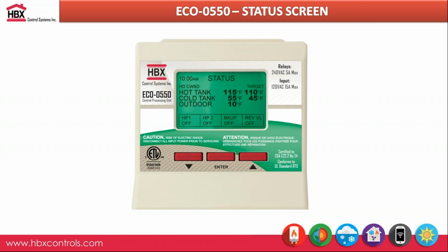The 4 boxes at the bottom of the screen act as your system function screen, so you can see what heat pumps are on and off, as well as your backup boiler, reversing valve, or your system pump, depending on how many heat pump stages you're controlling on there. One of the cool features that we add is that you can also have a multicolored backscreen display on the Eco 550. So depending on what the system is actually doing, it'll change that color.